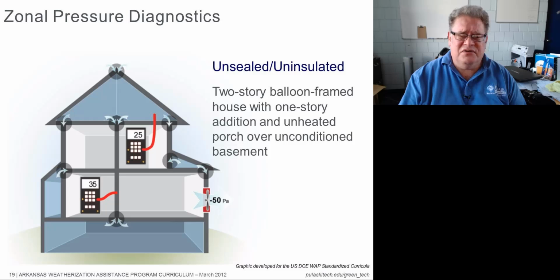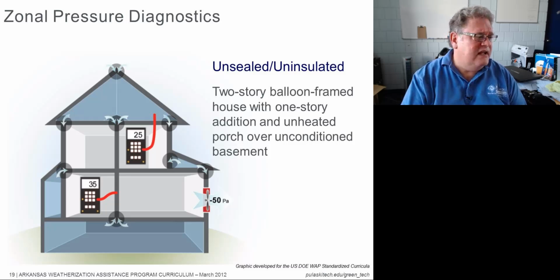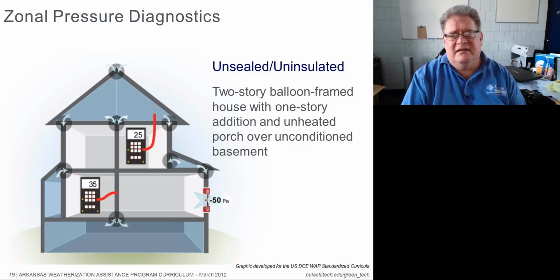This illustration is a 2-story balloon frame, and we are seeing lots of areas where air can move. This intersection right here, this intersection right here, this intersection right here, all of these are places where air can get in. If we have a porch that's attached to the house, generally that does not have any kind of siding or air barrier. The insulation is not going to work as effectively, especially if that's a vented porch. Air is going to move in there and the stack effect is going to take over, and we're going to have air move in through the ventilation at the soffit and right up that wall and into the attic. And that's going to cause this wall right here, this room, to be thermally or radiantly coupled to that wall. So it will always feel warmer or feel colder when an occupant is in there, and it'll probably be a room that's harder to heat or cool.